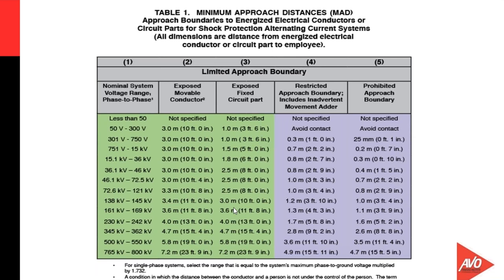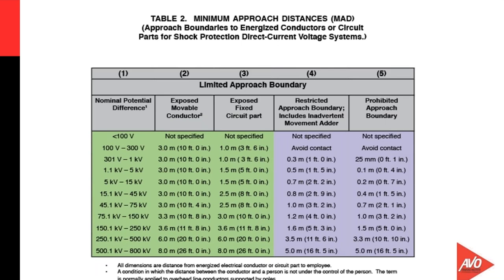If we're setting up a significant amount of test equipment in an area, then we have to have enough room to functionally use the equipment and to be able to move around in the test area too. So those are things that limit or dictate basically how large this test area may be. This is the approach distances to direct current voltage systems, and you can see it's similar in nature. And on the green side, we're talking about the limited approach boundary to either movable or fixed parts by unqualified persons, and that should have a bearing on our test area protection.